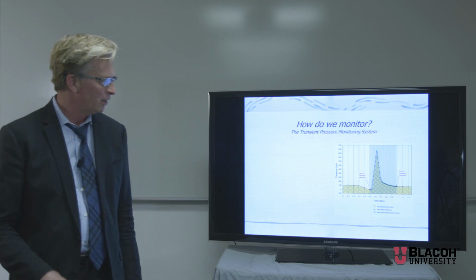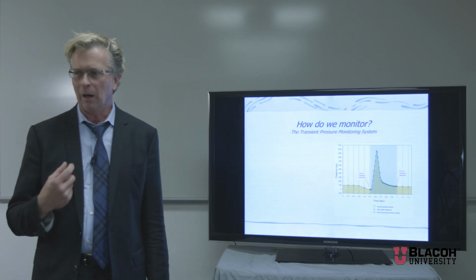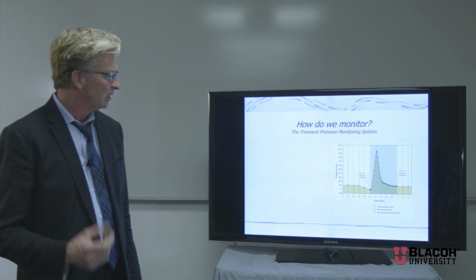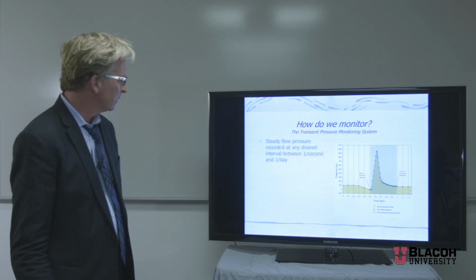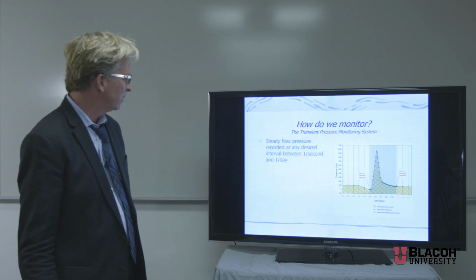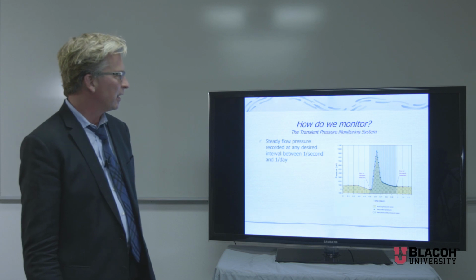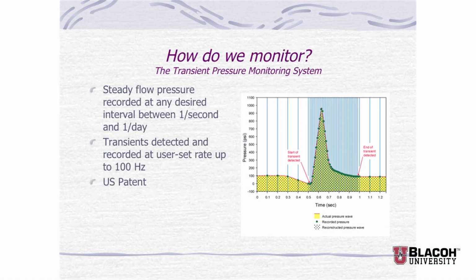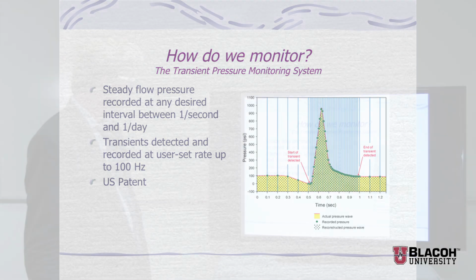So how we monitor is we're looking for that upsurge, downsurge, and then change our recording rate. And it'll take a running average that you can record, once a second to once a day, depending on the system. Transient records at up to 100 hertz.